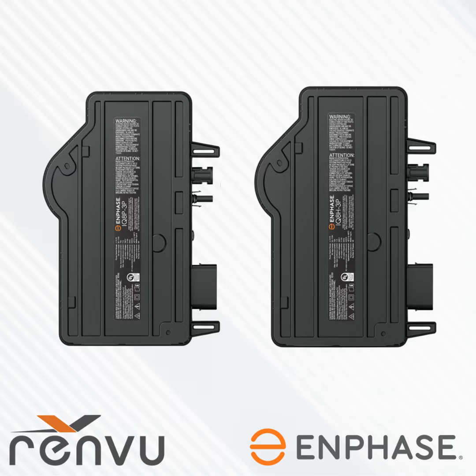In order to wire our micros together, we have this wire called QD cable. QD cable is the 4-wire 3-phase AC bus that collects all of the microinverter output and sends it to a subpanel. Enclosed inside that sheathing are 4 number 12 conductors, and that wire size requires a 20-amp breaker. The QD cabling is unique in that it provides the needed phase rotation built in to properly distribute power over 3 phases. So if you've used Enphase for commercial before, let's say you're using an IQ7 series and you had to move breakers all over a bus bar in order to get balanced phases, you don't have to do that anymore. We figured that out for you. We've made this product as easy as our residential.